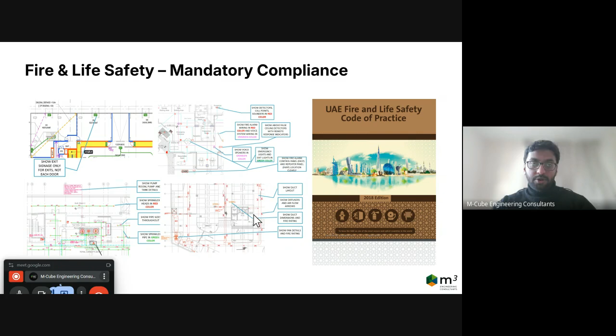Again, some of the important aspects which you need to look out for in the fire and life safety design is the LSR, life safety drawings. Ensure that you are working with the architects and complying with the minimum requirements of travel distances, dead end distances, common path. Ensure that the proper redundancy is mentioned in terms of the pump. If you're going with a super high rise building, you will have your diesel pump, electrical pump, jockey pump. In certain projects where you have a 50 GPM pump, they generally go with an electrical pump and diesel pump. So depending on the building classification and the type of project you're working on, the redundancy, the type of pumps and the flow need to be clearly identified from the codes.